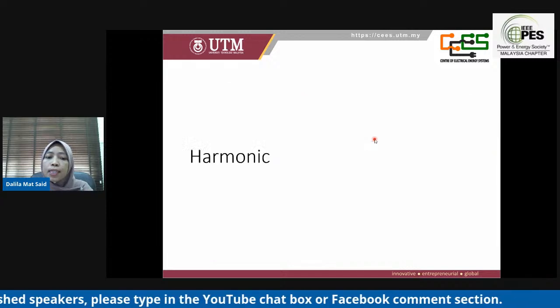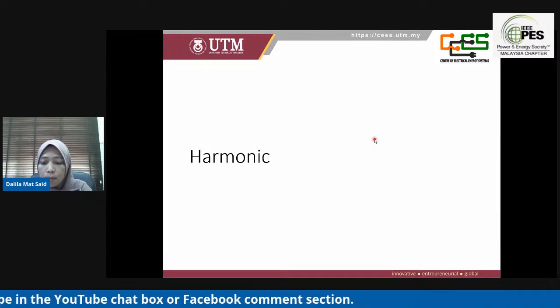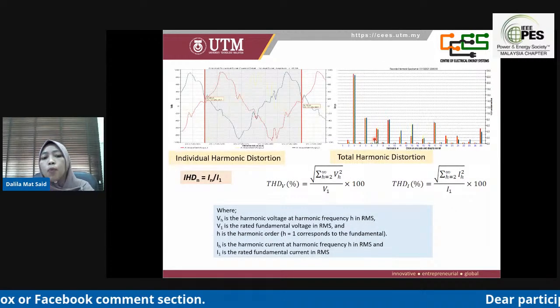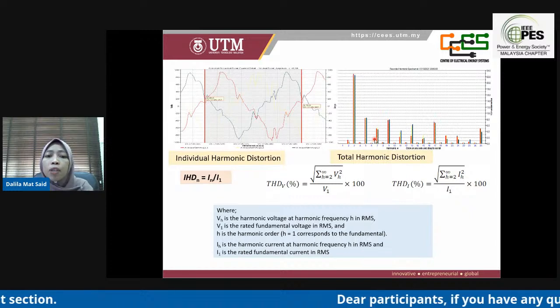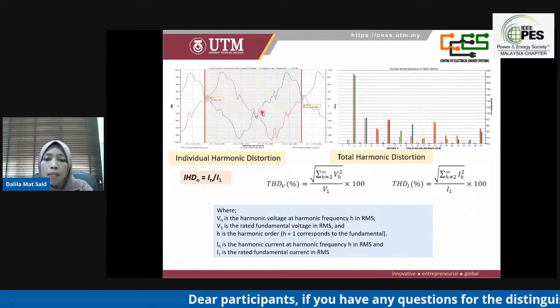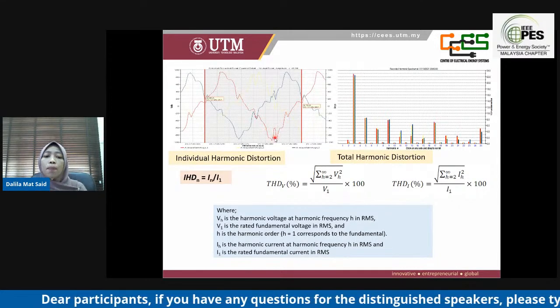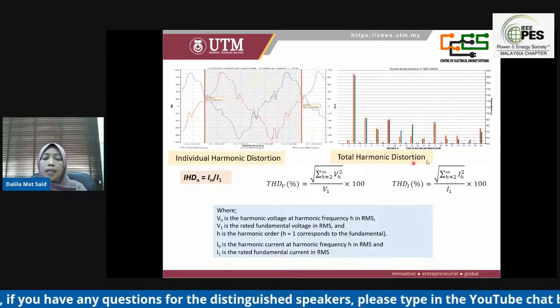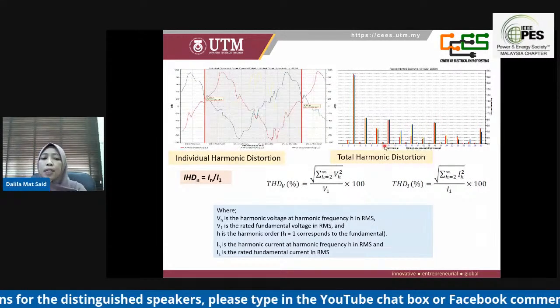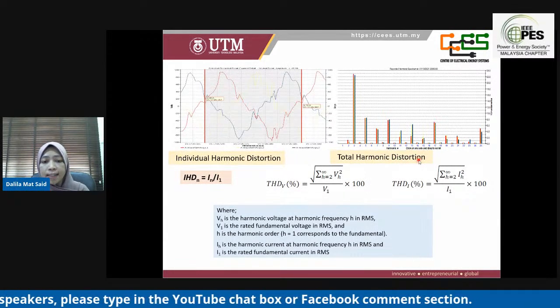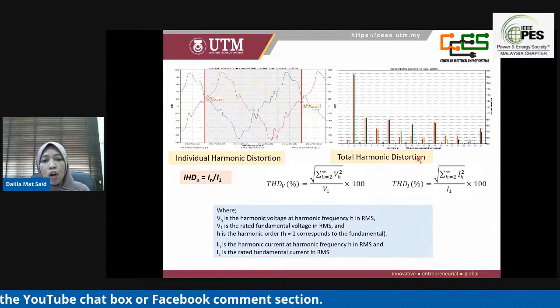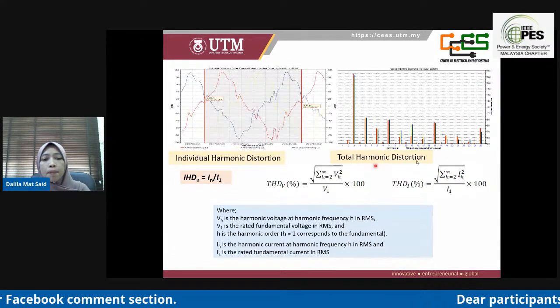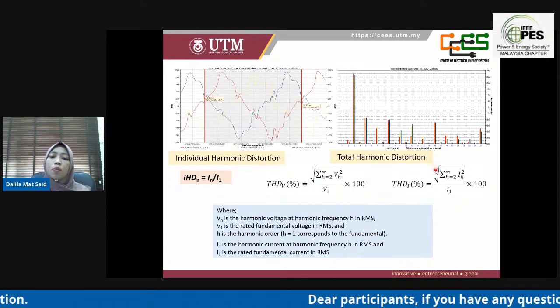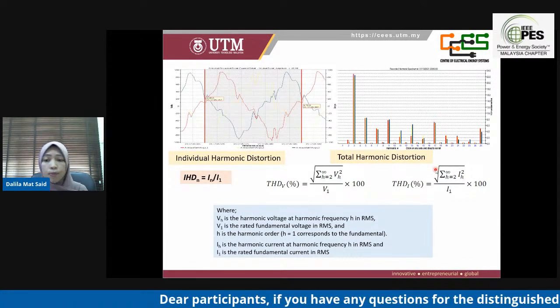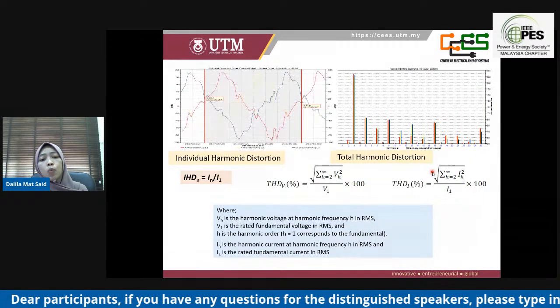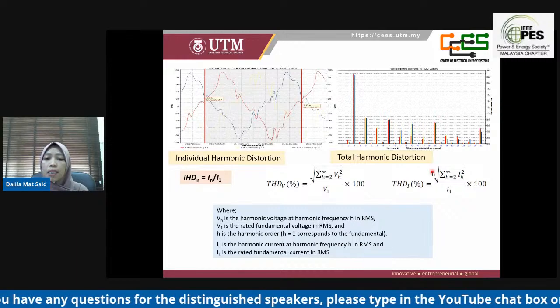So next we go to the second part of data analysis, which is harmonics. We can represent harmonic data in either the time domain or the frequency domain. Usually the time domain is known as the harmonic waveform, and the frequency domain is known as the harmonic spectrum. From the spectrum, we can see in detail the contribution of each harmonic order, and the harmonic number indicates the harmonic frequency. The first harmonic is the fundamental frequency, such as 50 Hertz. The second harmonic is the component with frequency 2 times the fundamental, and so on.